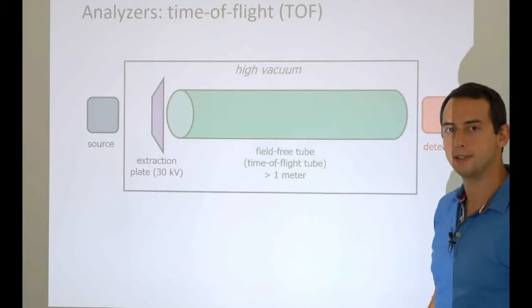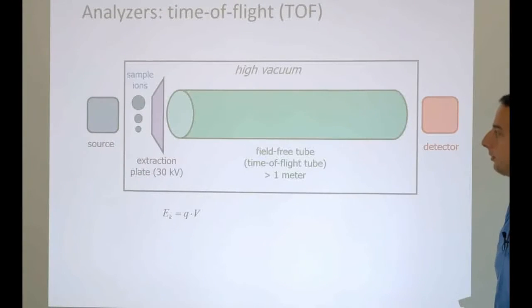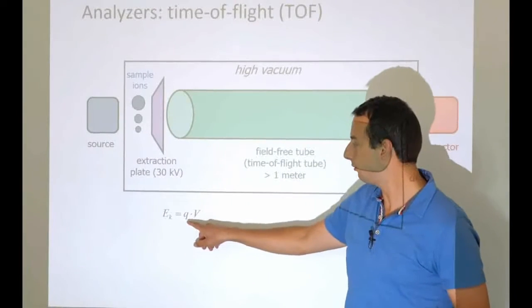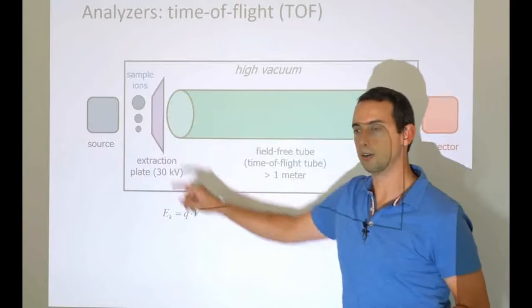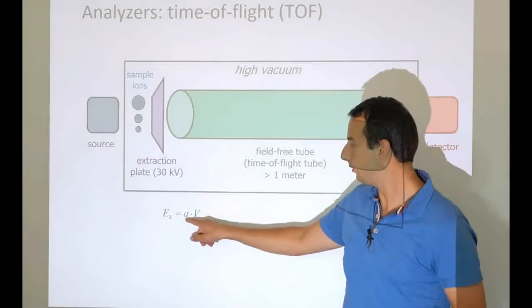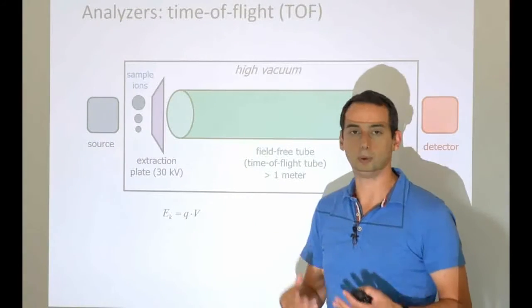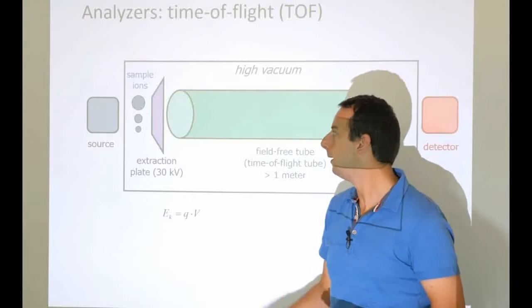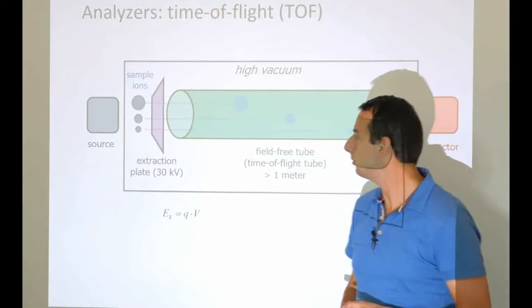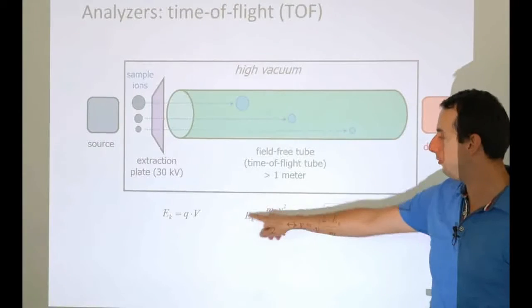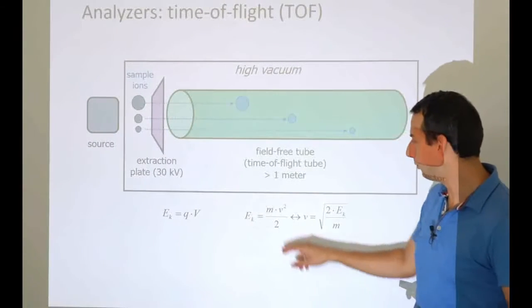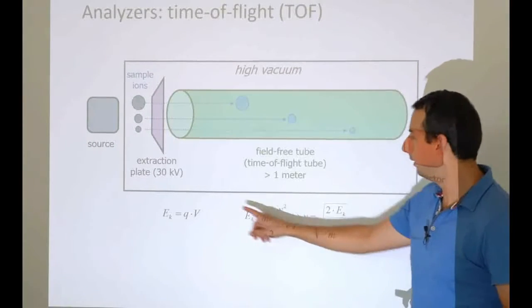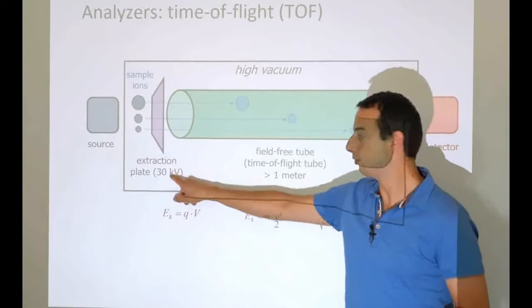Let's have a look at a small animation to see what happens in this time-of-flight analyzer. We have our sample ions, and they are being moved by the extraction plate. They receive a kinetic energy that is equivalent to the charge of the individual ion and the voltage that we have applied — so the strength of the field and the charge. Obviously, if you have twice the charge, you will feel the field twice as strongly. A 2-plus ion will feel the same field with twice the strength of a 1-plus ion. That is the kinetic energy that these ions receive. This kinetic energy is under our control because it comes from the voltage, which is something we set.